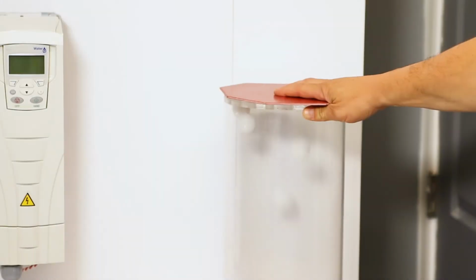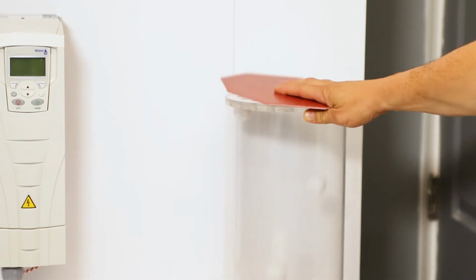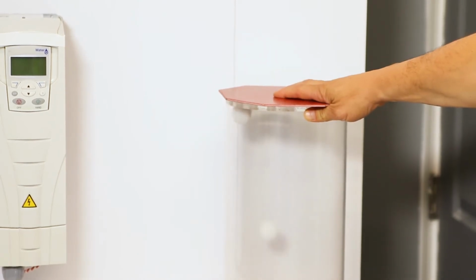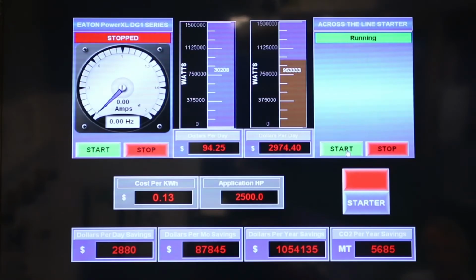Now I'm going to start this drive, and you'll notice that as the ping pong balls are bouncing around in there, I can adjust the speed to make it whatever it needs to be. If I want to, I can try to match that with the ping pong balls over here bouncing around. When I do that, you'll see that I'm only using about a quarter or less of the energy to do the work on the drive as I am with the damper on the airflow system here. So it's very clear that using the reduced speed on the drive saves a significant amount of energy compared to the damper on the ping pong balls on this side.